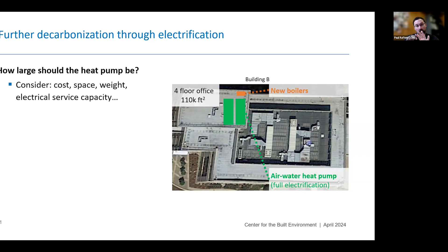sizes. So for some context here, this is the air-to-water heat pump if we were to fully electrify that building with exactly the same capacity as the boilers that we installed. So we also, in our analysis, wanted to assess a partial electrification case where you would keep the same boilers, but you would install a relatively small heat pump to try and operate that as efficiently as possible and offset as much of the gas use as we can, while still keeping the size of the equipment to the point where it would be more feasible to install. The heat pump we modeled in the partial electrification case is about 14% of the installed boiler capacity, which, because of the redundancy requirements in this plant, is about 20% of the peak load.